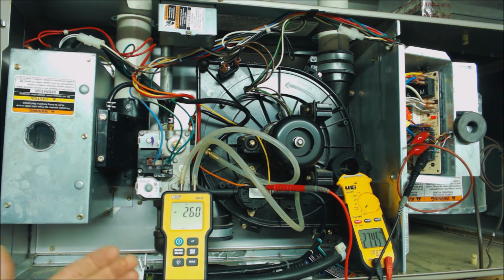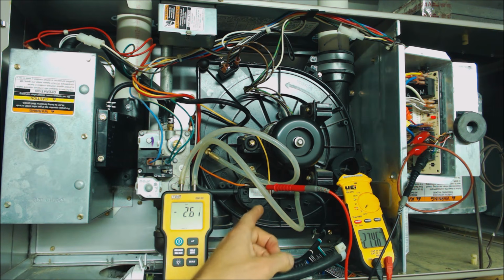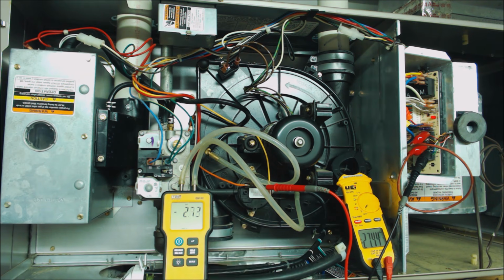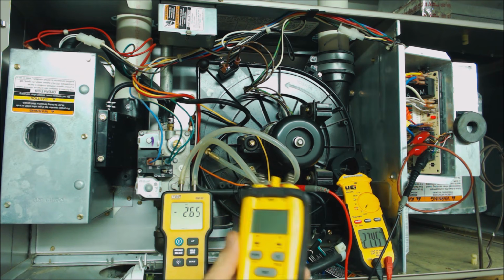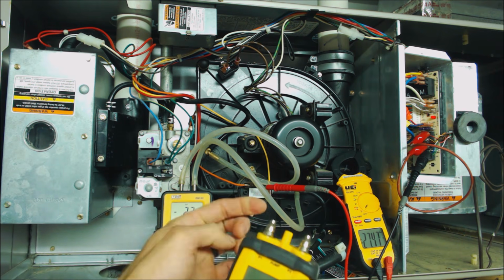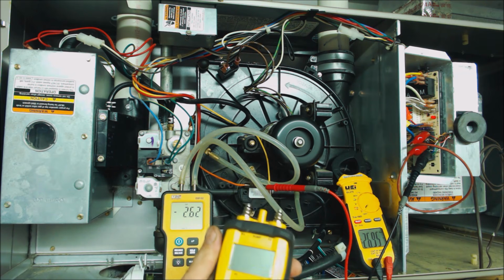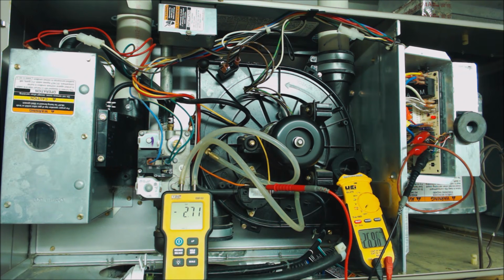air. So if we read this from the beginning, say we read negative 2.6 or we read negative 2 inch water column across this pressure switch, but the pressure switch was not allowing the voltage to go across it, that's how you'd know that the pressure switch was bad. You could also test the pressure switch with a digital dual manometer like this, because it has a pump. You can actually disconnect the pressure switch completely, and this pump will be able to create the negative water column readings in order for you to test the pressure switch.